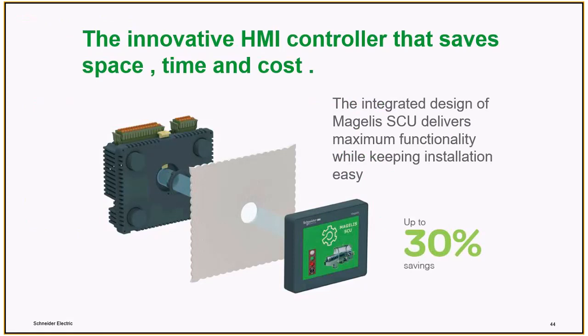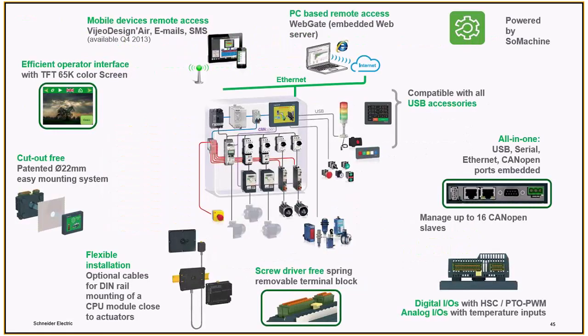This is another interesting offer — a controller based HMI. With Industry 4.0, this offer has Modbus TCP/IP communication and RS-232, where I can connect to a GSM modem. I was talking about SMS alerts to a maintenance engineer — using this offer, I can generate an AT command and pass a message to a maintenance engineer, with priority based, hierarchy based alerts.